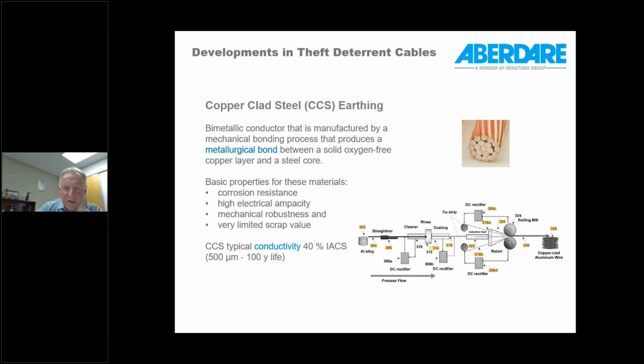This is not plating, it's not an electrolytic process. It's a mechanical means of applying copper strips to a very clean substrate of steel, or aluminium alloy in the case of CCA. This picture shows aluminium alloy, but the process is exactly the same also for steel. So the input here would be steel and the output would be copper-clad steel. Under high temperature and high pressure, these copper strips are applied onto a metallurgically clean steel substrate, pressed together and then immediately drawn down to smaller sizes, so that there's a metallurgical bond between the two materials.